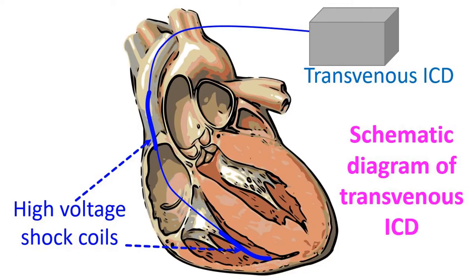Left-sided implants are preferred because ICD shocks will be more effective with an ICD pulse generator can on the left side. ICD pulse generator can is one active electrode, while high voltage coils located in superior vena cava and right ventricle are the other active shock electrodes for a transvenous ICD. Overdrive pacing for ventricular tachycardia is an option available in transvenous and extravascular ICDs, but not in purely subcutaneous ICDs. Overdrive pacing is a painless form of treatment for ventricular tachycardia, which is not too fast.